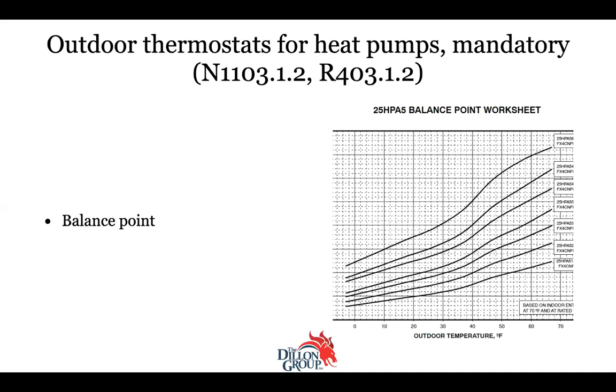Wow. I just learned something already. I knew there had to be a lockout to prevent the strip heat from coming on when the heat pump could handle the load. But I just thought it was an on-off. I thought it sensed when it could, but it's actually a setting that needs to be adjusted. Yeah, they can just adjust it to fit. So if the system can handle it, you don't have to kick on the strip heat. Because it's really not a lot worse than trying to heat your house with a hair dryer.